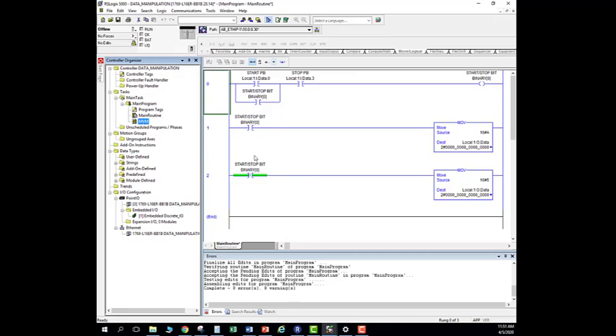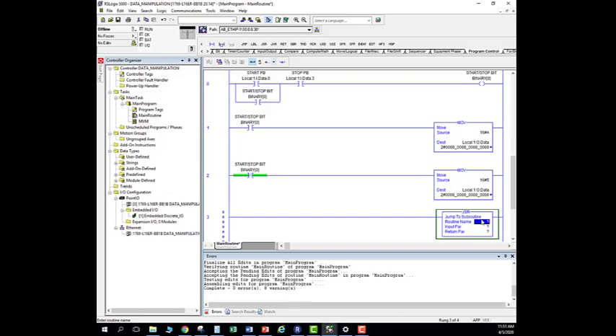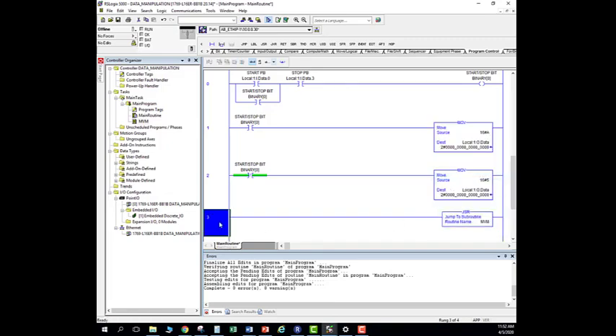MVM showed up here. Next thing I'm going to do is create a new rung. I need to go to Program Control — remember this from last class period — Program Control is where I find JSR jump subroutine. I'll select it, find MVM, and remember before we had to remove instruction parameters, so I'm going to go ahead and remove instruction parameters. Now I'll go ahead and download this information so now I'll have my MVM populated and running.